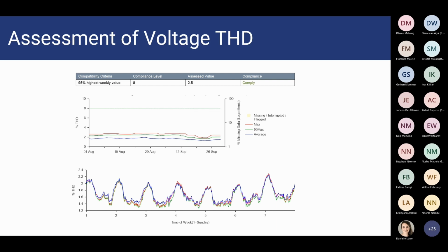The bottom graph here, that you also get from our report that you can generate automatically, shows you, for this month period, how your voltage THD looks in a typical week. What you can see here is how the THD decreases during the day, but actually increases during the nights. This is something you can commonly expect at points where there are industrial loads, because large industrial loads normally during the day cause damping. That damping will then lower your THD, leading to higher values during the night when the damping on the network is lower.